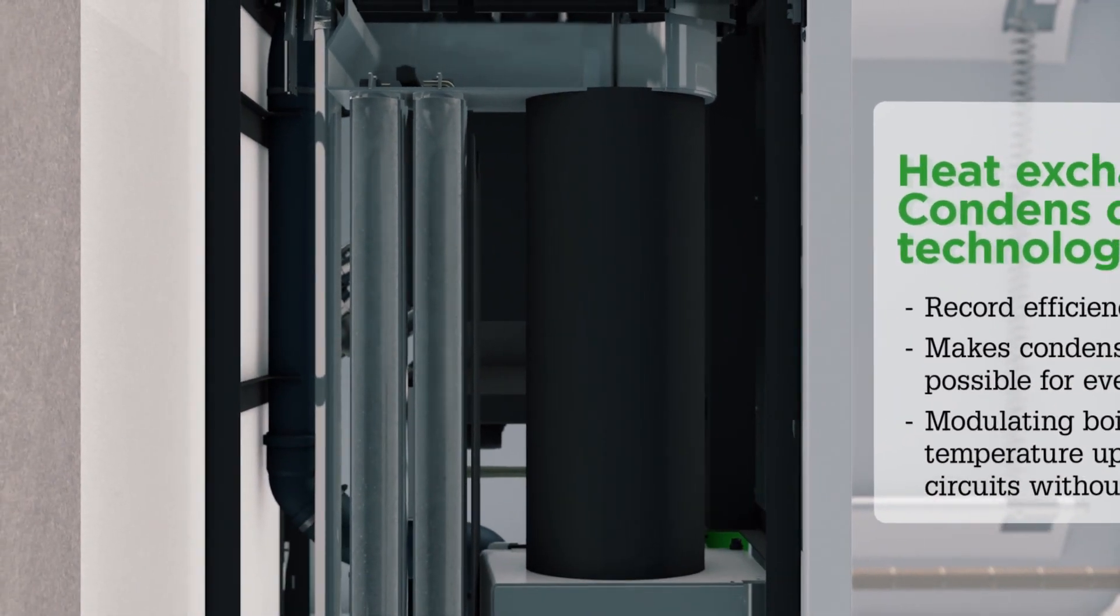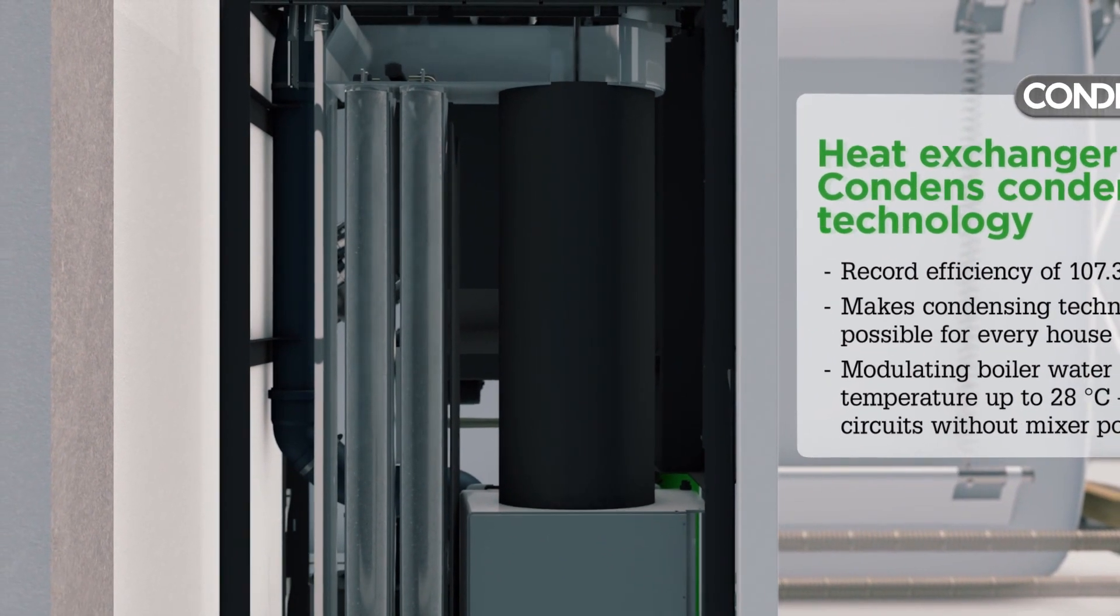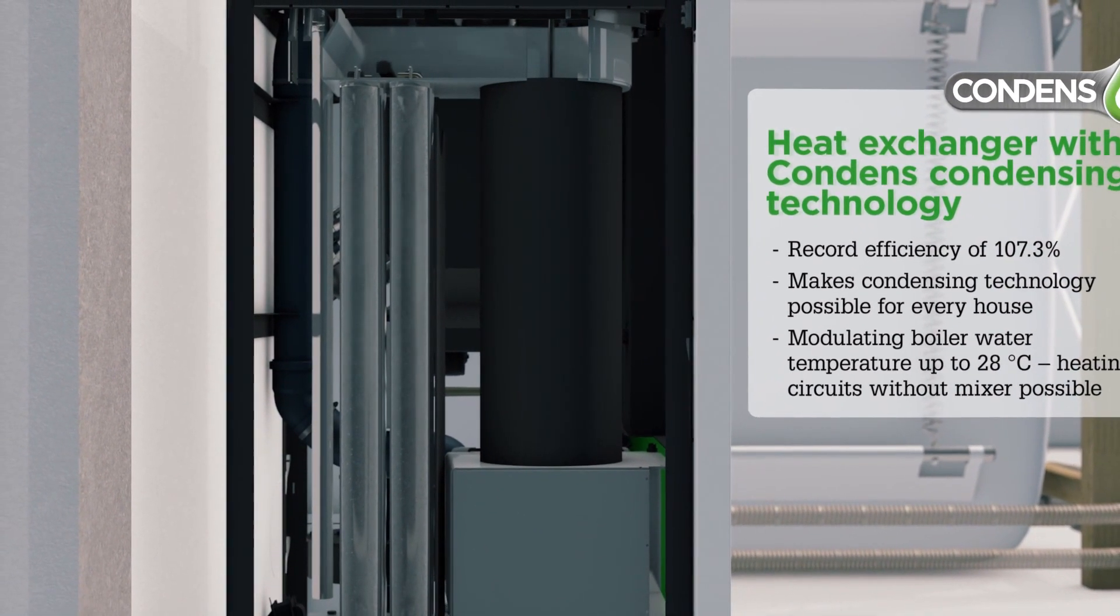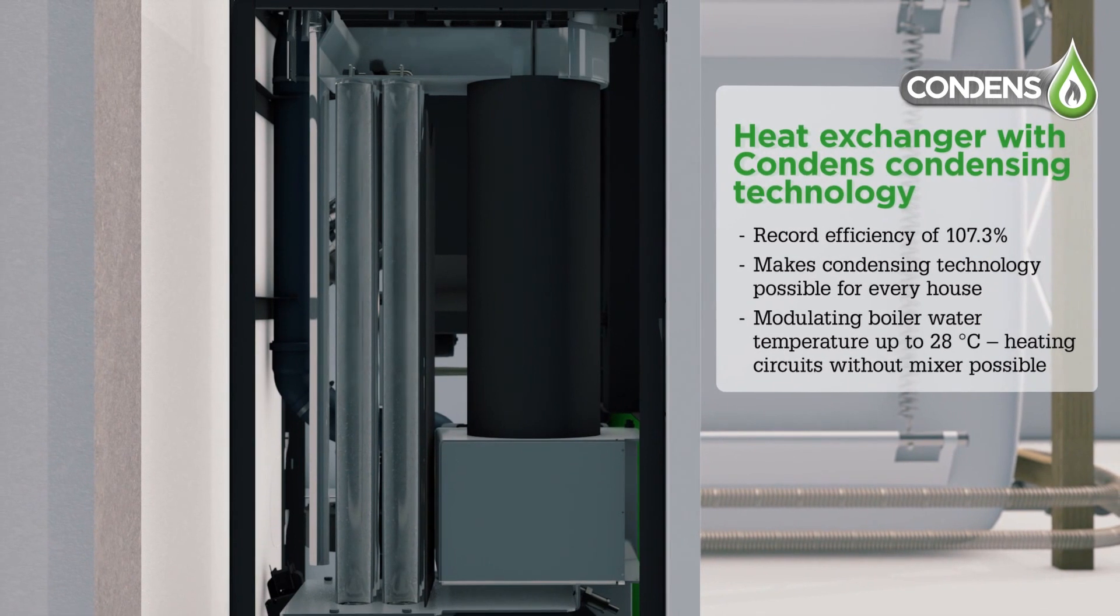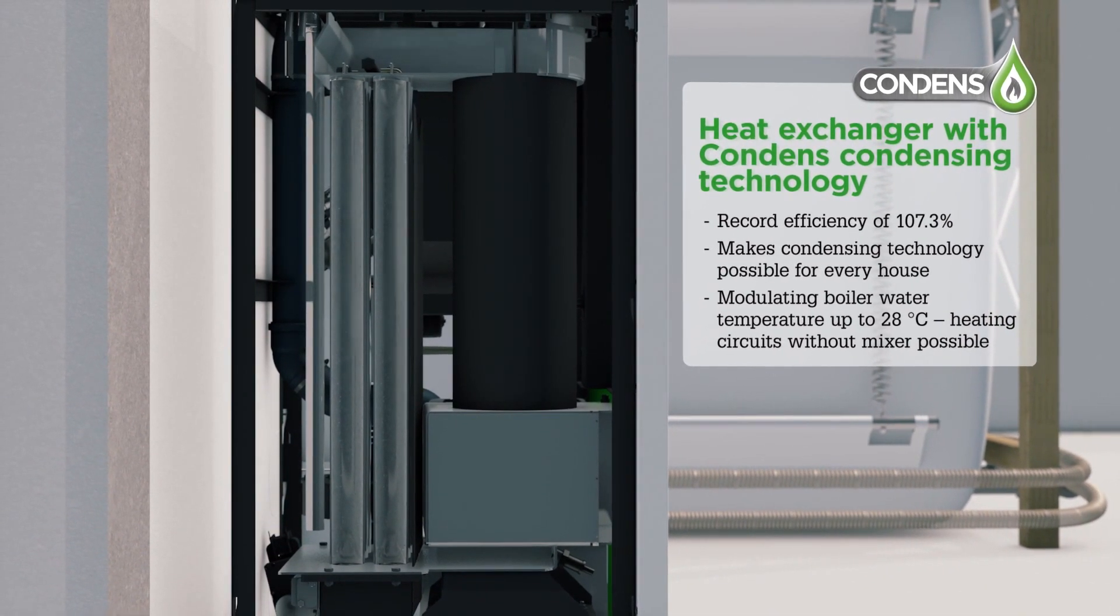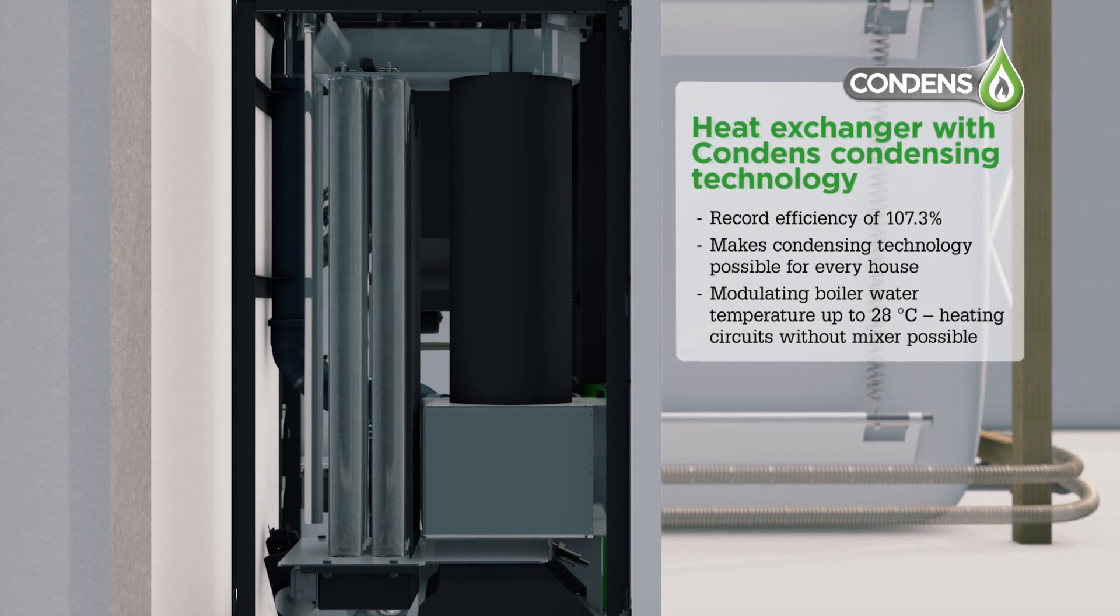For the first time it's been possible to develop a pellet condensing boiler system that can be installed in any house regardless of whether it's equipped with radiators or underfloor heating. The high quality construction in stainless steel enables boiler operation at a temperature of only 28 degrees, thereby allowing radiators to be fed directly with no need for a mixer valve.